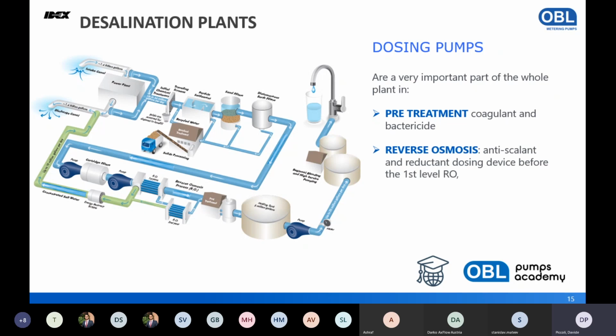In reverse osmosis, there is a big need to dose antiscalant to avoid scaling formation before the first level of reverse osmosis. In the second level of reverse osmosis shown in the scheme, the need is to adjust the pH, so there's also a need for caustic soda or acid adjustment. The last part is the boiler feed water, which we'll see later, because here there are again big boilers to warm the water before treatment.